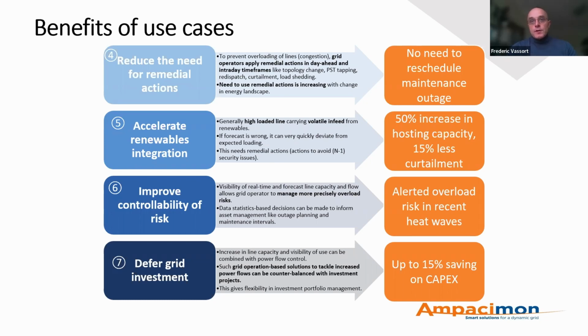Renewables integration is a very important topic, because most of the value of DLR is due to wind cooling the lines. It's natural that if wind blowing on lines increases their capacity, the same wind also blows on wind farms, so there's a natural correlation between hosting capacity of wind farms and DLR. We have numerous examples showing that if DLR is used on lines adjacent or close to wind parks, we can increase hosting capacity by as much as 50%, or reduce curtailment of existing wind farms by as much as 15%.